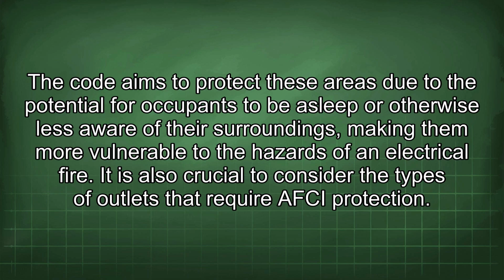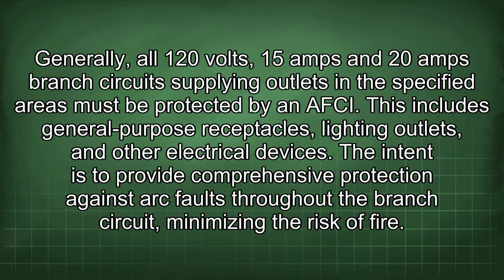It is also crucial to consider the types of outlets that require AFCI protection. Generally, all 120 volt, 15 amp and 20 amp branch circuits supplying outlets in the specified areas must be protected by an AFCI. This includes general-purpose receptacles, lighting outlets, and other electrical devices. The intent is to provide comprehensive protection against arc faults throughout the branch circuit, minimizing the risk of fire.